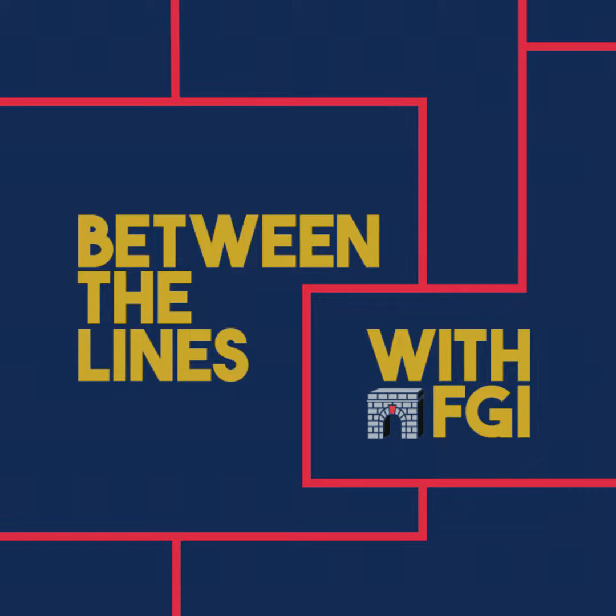So that room is already filled with 1x atmospheric air, and now we're going to fill it with 3, 4, 5x additional of gaseous helium. We're going to pressurize that room. So in the Wayback Machine, when I advocated so vocally for outswinging doors, the idea was that if the pressure builds up inside the room, it wants to help the door open, it wants to push it open, and you get sort of natural passive pressure relief.